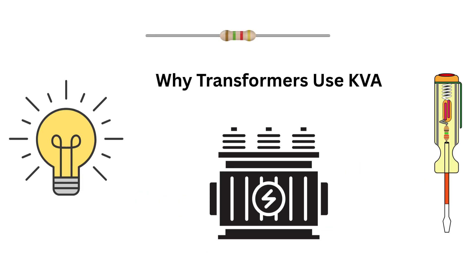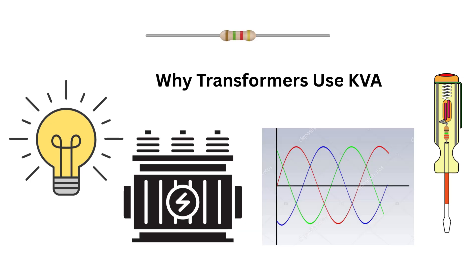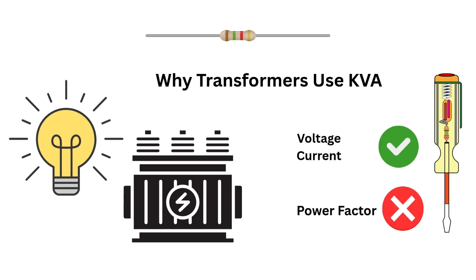So a transformer's job is to transfer electrical energy from one circuit to another without knowing how the power will be used. It doesn't care if the load is resistive, inductive, or capacitive. Because a transformer doesn't consume power — it only carries it. Its rating depends on voltage and current, not power factor. That's why we use KVA, not Kilowatt.